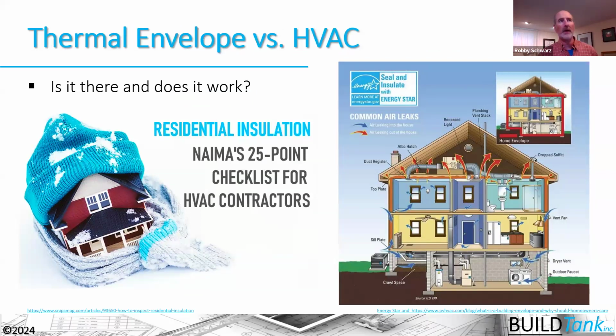So asking that question when we're looking at the construction of the building thermal envelope: is it there, and does it work? We talked about that focus on performance and the inspection process and the building process, so that we can determine, has the insulation been installed, but has it actually been installed so it performs? Are the bath fans installed so they can actually perform? And we take that same concept to the HVAC when we're talking about duct systems or hydronic systems or heat pump systems. We can't just install something and assume it's going to perform. We need to do some level of inspection and testing and ensure that it's going to perform as intended. And that whole idea that we get what we inspect, not what we expect.